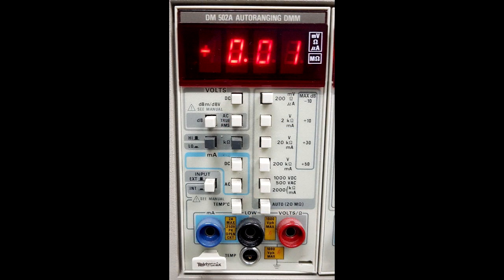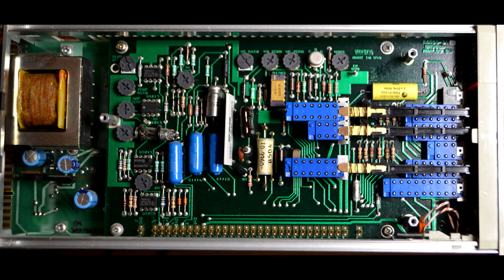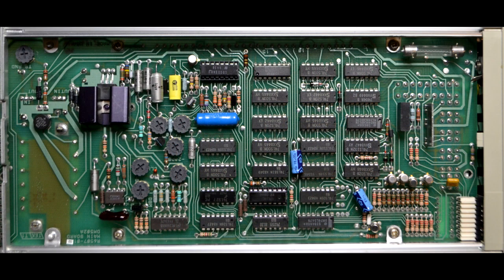Compare this with the front panel of a DM502A. It has twice as many buttons and a few more features. The 502A has rear interface connections, 2 resistance voltage measurement settings, and an AC volts dB function, all lacking in the DM504A, but most users won't miss these functions. The DM502A has 3 circuit boards, an analog board, a digital board, and a small display board. Note the 16 calibration trim pots.